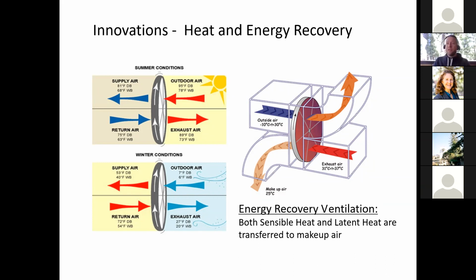And so as moist air passes over it, through it, it actually wrings out the moisture and absorbs it. And then as that desiccant moves to the other airstream, where say you have hot air leaving the building, it will actually dry that desiccant out. And so the moisture will transfer to the outgoing airstream. These can be used for energy recovery, heat recovery, or both, depending on the velocity that you turn that wheel. So the faster the velocity, the faster that wheel moves, the less moisture it removes, but the more heat it will transfer to the other airstream.